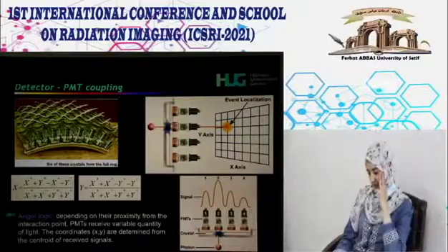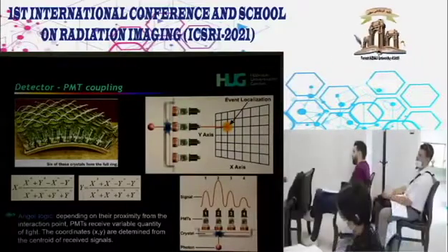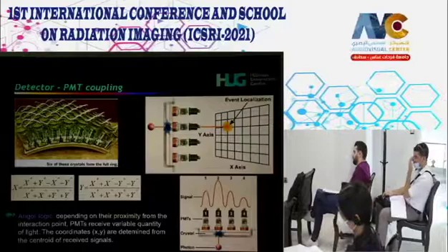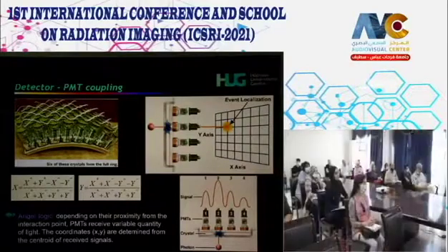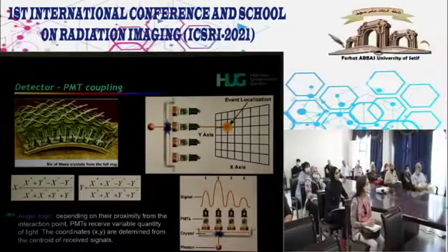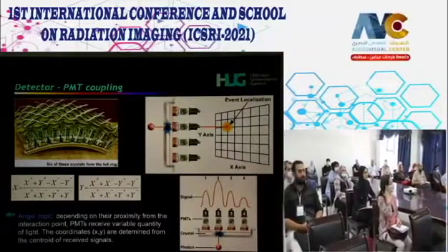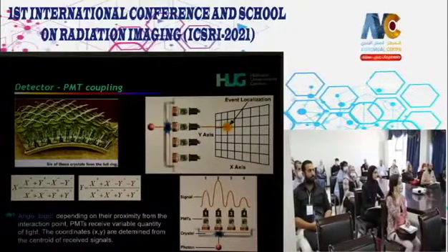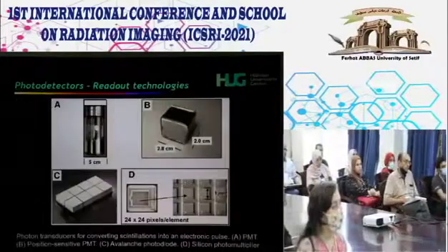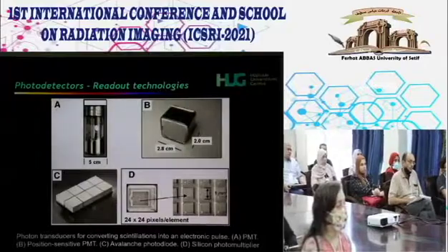Right, so this is a really conventional technique implemented on almost 100% of the conventional gamma cameras that we use in the clinic. It's basically a mixture of small resistors, so it's not really high-tech stuff. Good. So now coming to the readout technologies.